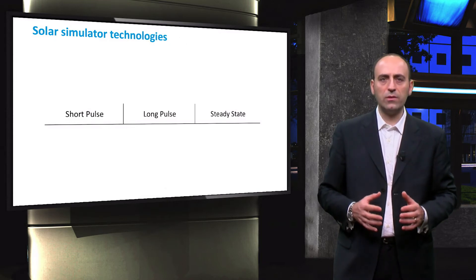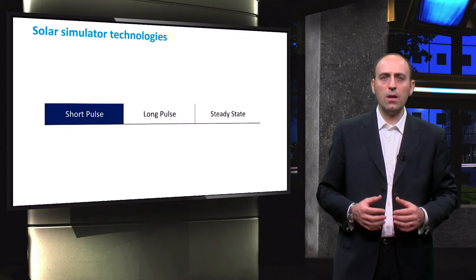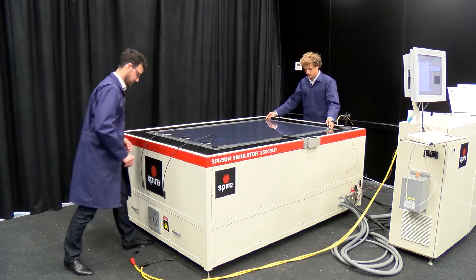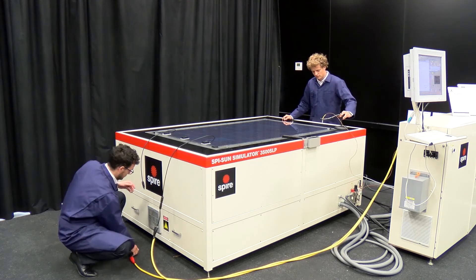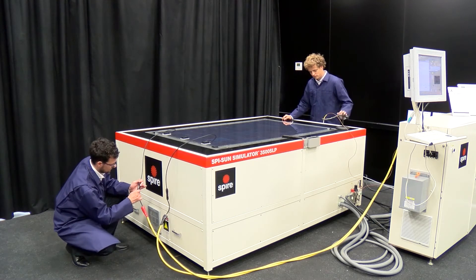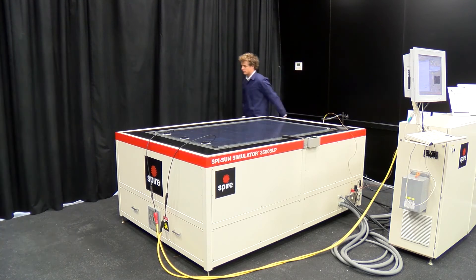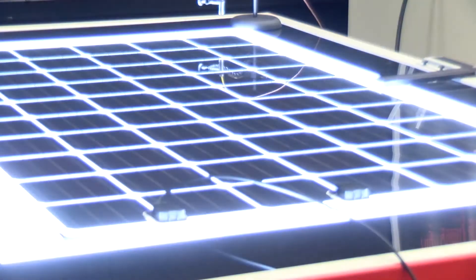Although the techniques are very different, they must comply to the same standards. Let's start with the short pulse, also called the flash simulator, which is qualitatively similar to flash photography, with a typical duration of several milliseconds, and it can reach very high intensities of up to several thousand suns. This type of equipment is often used to prevent unnecessary heat buildup in the device during the test.